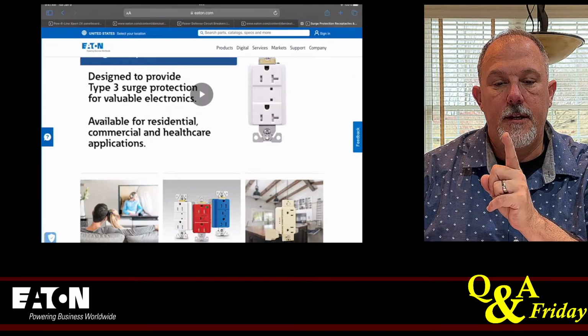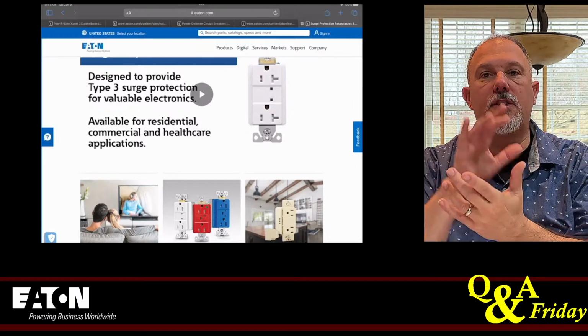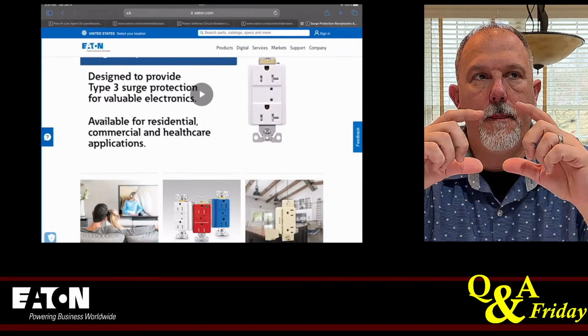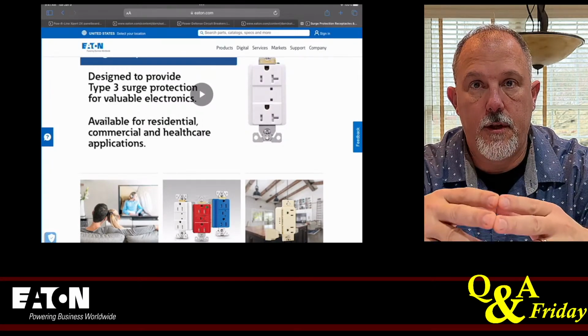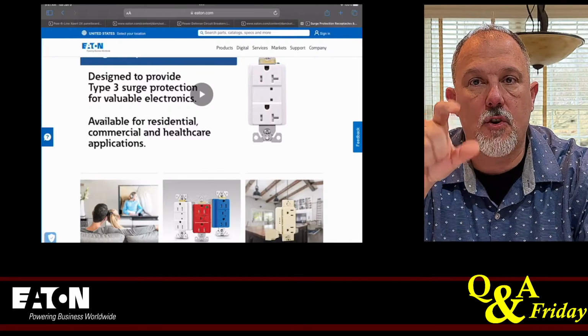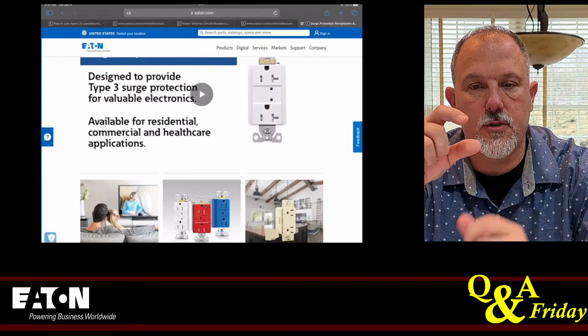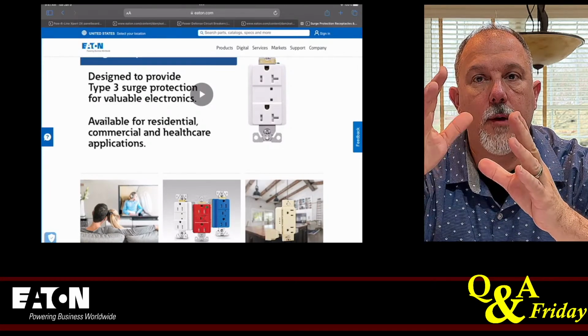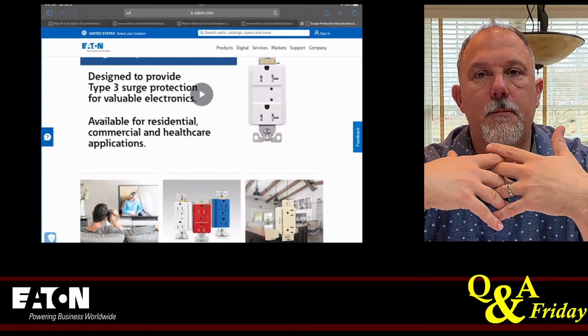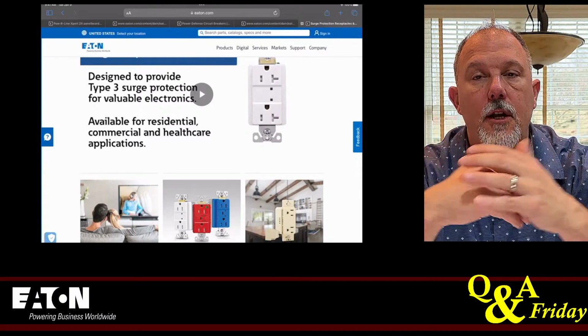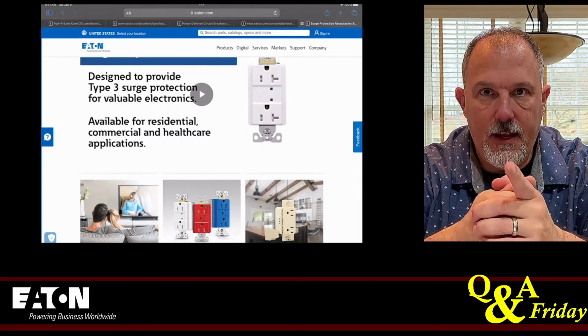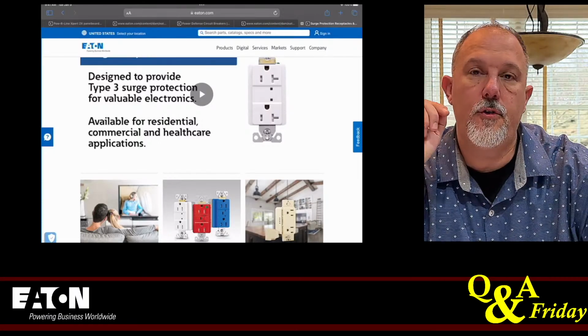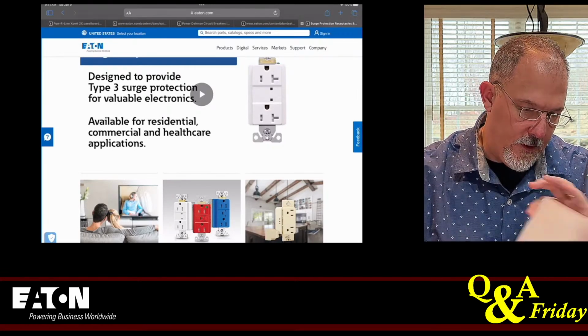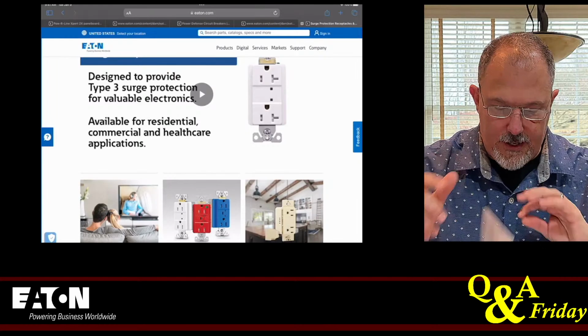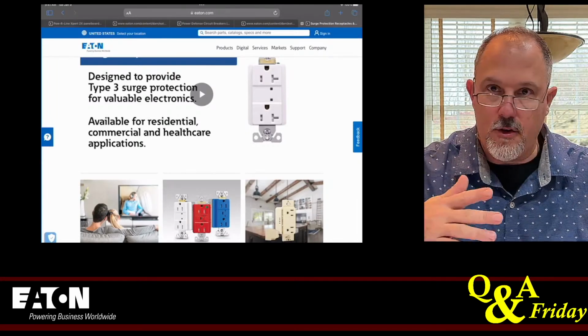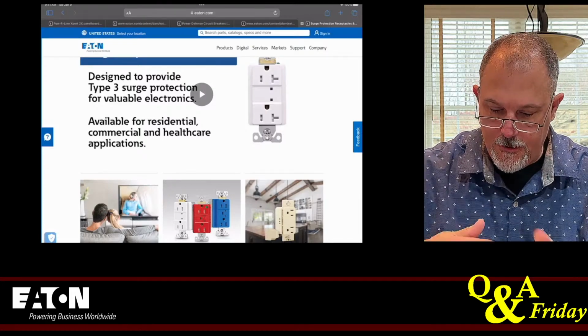The product, if you think about the way surge is made, a surge product is looking at voltage, and it's looking at voltage transients. You put the MOV across the terminals of the protected circuit, and then it will clamp that voltage. So it's typically in parallel with the circuit. You're not in series. If you have a 15 amp or a 20 amp receptacle, you would follow the rules of what can be fed from a receptacle perspective and what you can put on which branch circuit and their ratings based upon the requirements found in 210.